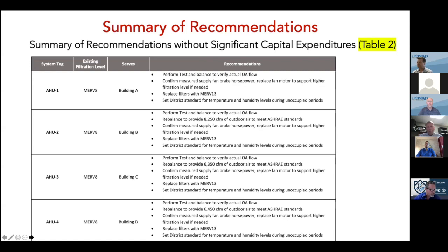So what happens is either you burn out your motor quicker or you reduce the number of air changes an hour in a classroom. And that is probably more detrimental than leaving the filters as is. So we don't want to reduce air changes or reduce the outside air ventilation by putting in higher MERV rating filters. The two should be performed together. So that's why we really want to look at fan motor horsepowers to determine if we can put in higher filters and collect some of those particles and viruses.